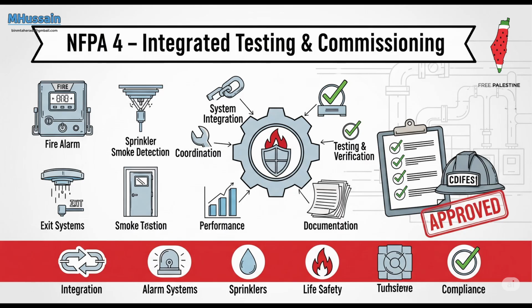Okay. To actually perform the tests, an integrated system test team must be established. That's the formal term. A whole team. Yes. And at a minimum, this team includes two key roles: the integrated testing agent, usually called the ITA, and then the installation, testing, or maintenance people for each separate system that's being integrated. So the fire alarm tech, the sprinkler tech, the elevator tech. Exactly. Whoever is responsible for each piece of the puzzle needs to be part of that team, though it's flexible too. On smaller projects, the standard says the owner or their representative can actually take on the ITA role themselves. Okay, so it scales a bit.